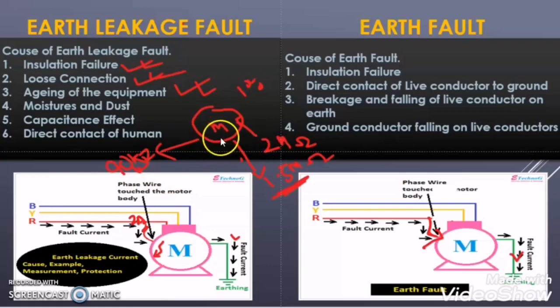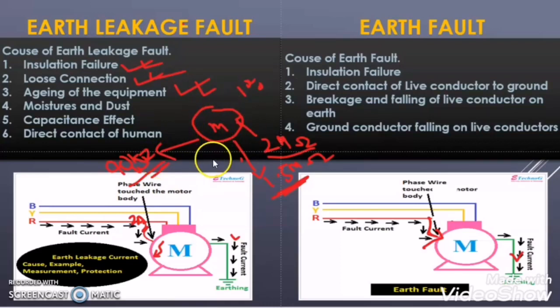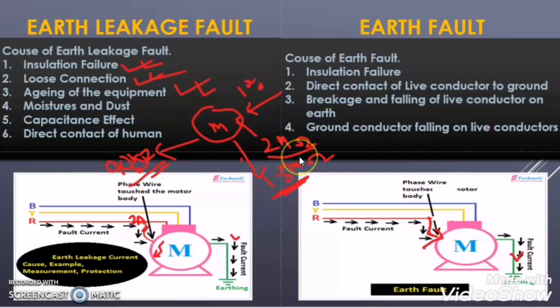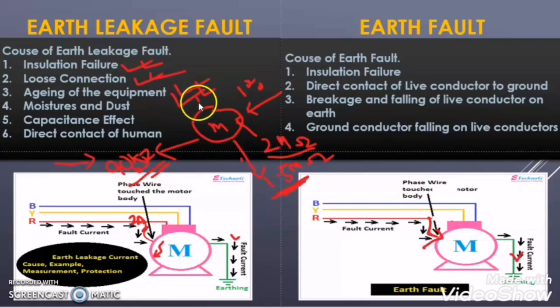But when we measure the insulation of the motor winding after 10 or 12 years, we find that the insulation of the motor winding came to 900 kilo-ohm. When the motor was new, the motor winding insulation was around 2 megaohm, but after 10 to 12 years of use the motor winding insulation came down to 900 kilo-ohm. So with time, the motor winding insulation gets deteriorated. When the motor was new, at full load current there was no leakage current, but after 12 years when running the motor at full load there is leakage current due to the deterioration of the winding insulation. So the third cause is aging of the equipment.